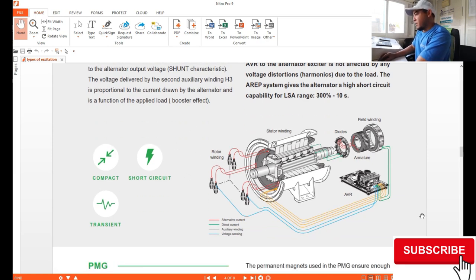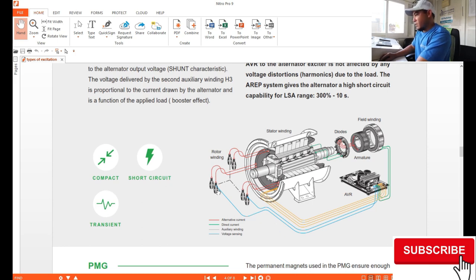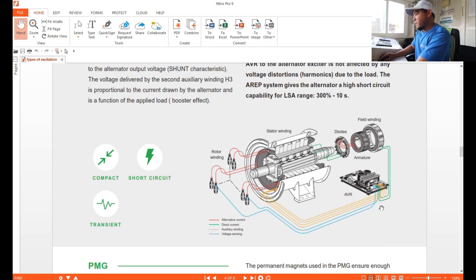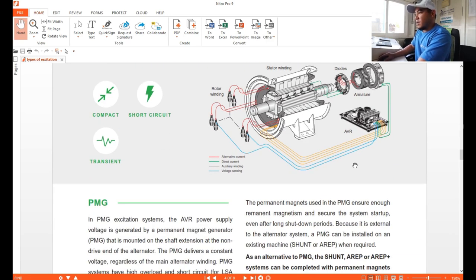Here are the AREP connections. As you can see, we have the same exciter field connections with two auxiliary windings added (the yellow lines). The rest is your voltage sensing. The number of connections is the same as AREP+, but the difference is that you have two auxiliary windings instead of one.